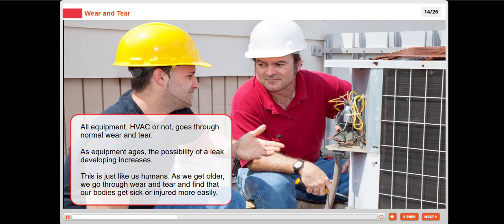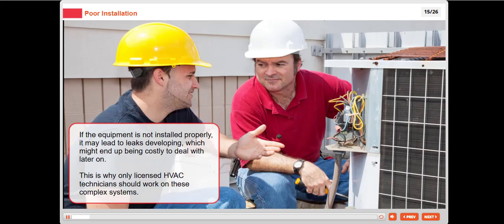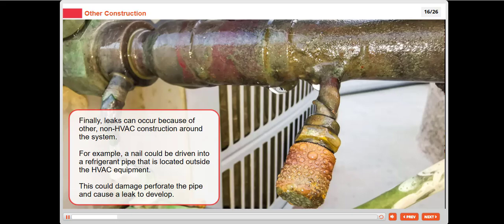This is just like us humans. As we get older, we go through wear and tear and find that our bodies get sick or injured more easily. If the equipment is not installed properly, it may lead to leaks developing, which might end up being costly to deal with later on. This is why only licensed HVAC technicians should work on these complex systems. Finally, leaks can occur because of other non-HVAC construction around the system. For example, a nail could be driven into a refrigerant pipe that is located outside the HVAC equipment. This could perforate the pipe and cause a leak to develop.